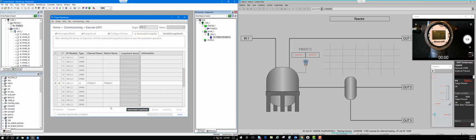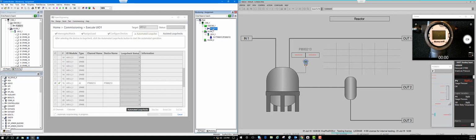Okay, so here it is, automatic loop checking in progress. If you notice here on the corner of the instrument, you do not see a D, which stands for loop test enabled, which is a manual milliamp output that the instrument is producing. So it should show up here. It takes maybe 5 minutes or so for the loop check to truly begin, and you'll know when it starts when you see your control strategy activate.